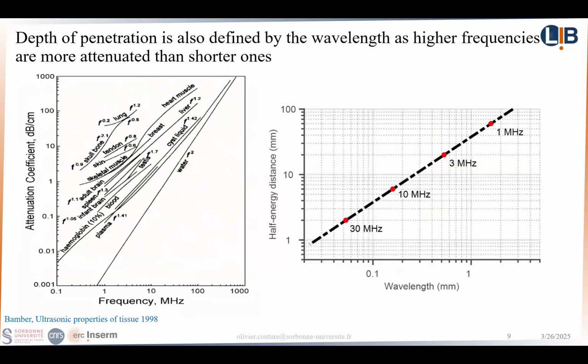Then there's the other part of the trade-off: as the frequency increases, as we shorten the wavelength, the attenuation increases quite drastically. And the worst attenuation that we will come in contact with is, for example, the skull bone, which attenuates ultrasound very rapidly. So we have to use a longer wavelength, a lower frequency, to have a better penetration. So this is the basis of the trade-off.